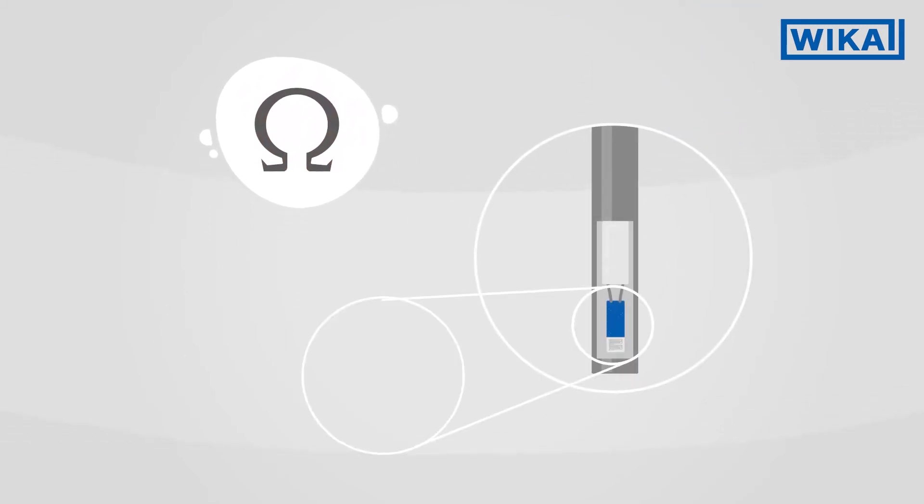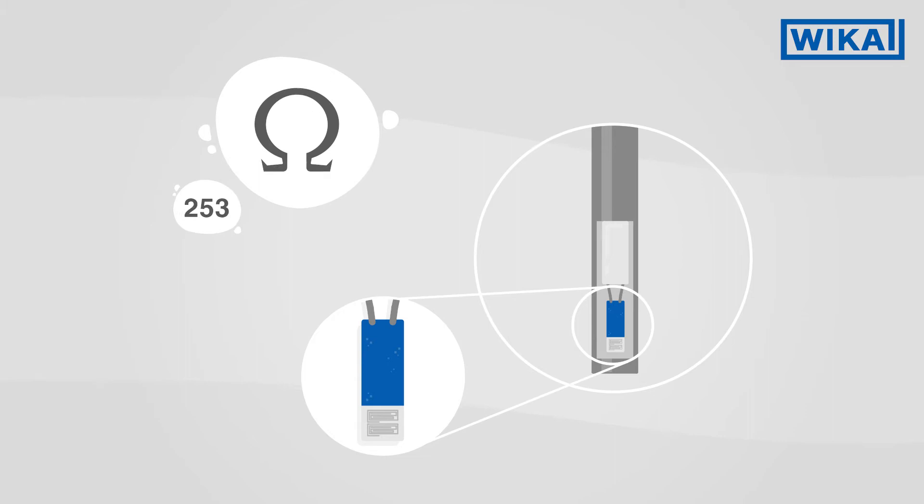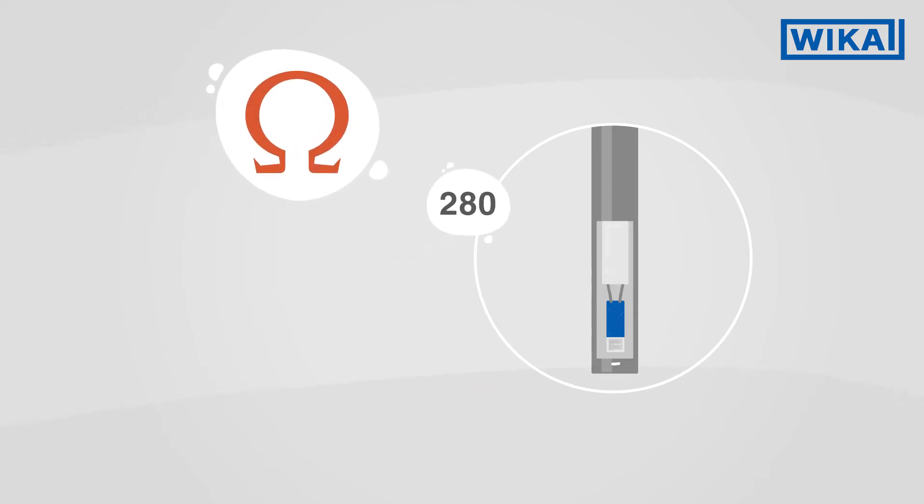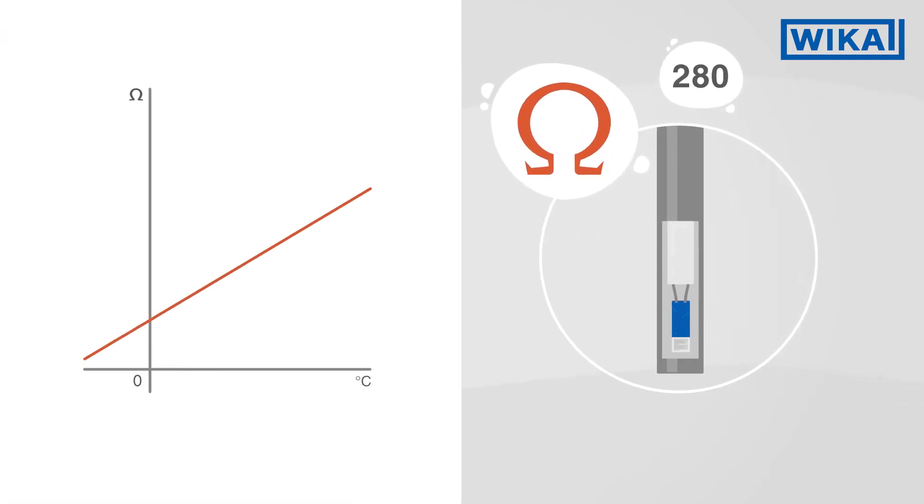The heart of a resistance thermometer is a platinum measuring resistor whose measured values are defined by standards. If the temperature changes, the electrical resistance in the sensor either decreases or increases following a precisely defined characteristic curve.